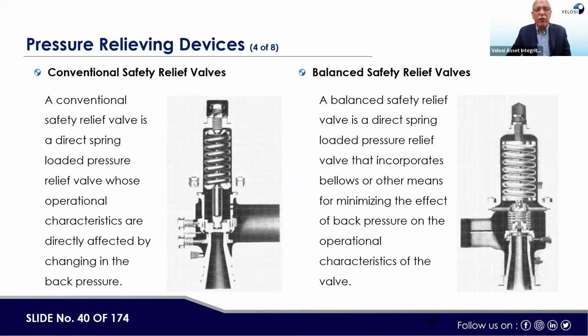Then conventional safety relief valve means, like again, being repeated. Like here, this is the inlet, this is the disc. This will press this spring where the set point. Then this goes up and fluid goes out. And this is a balance bellows.